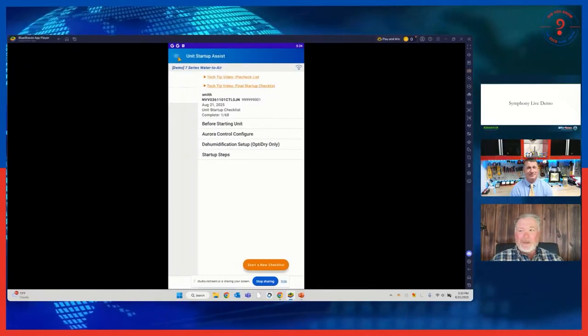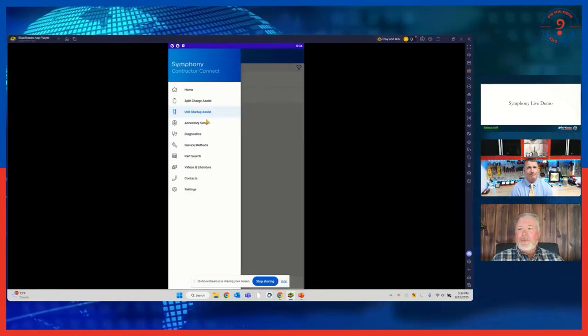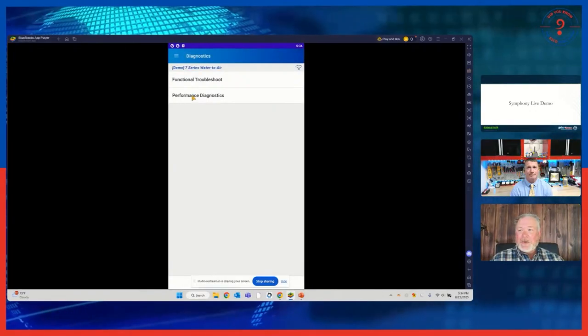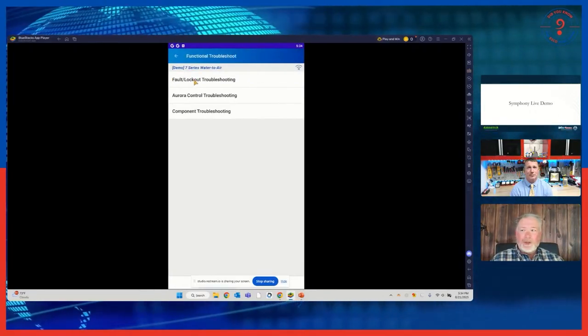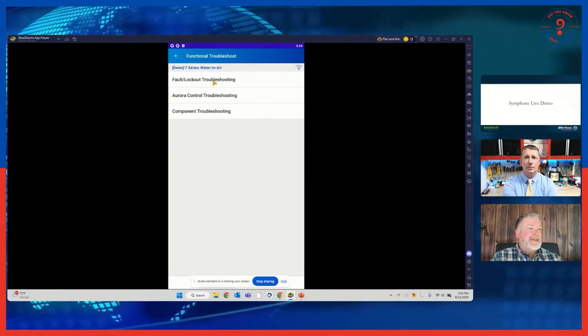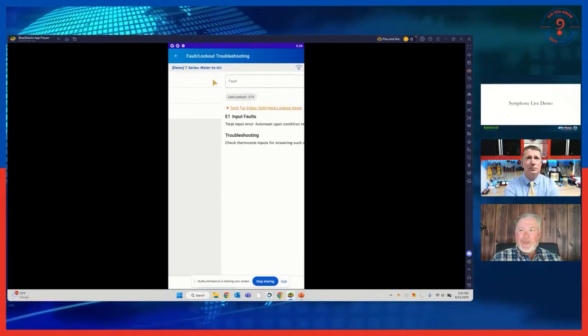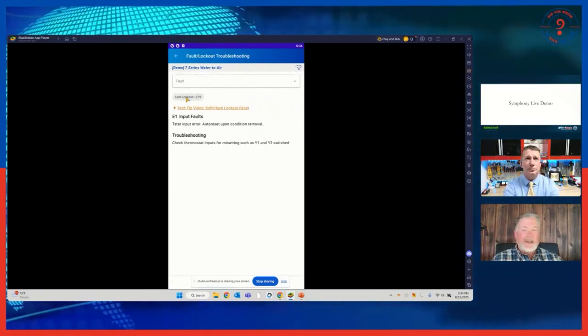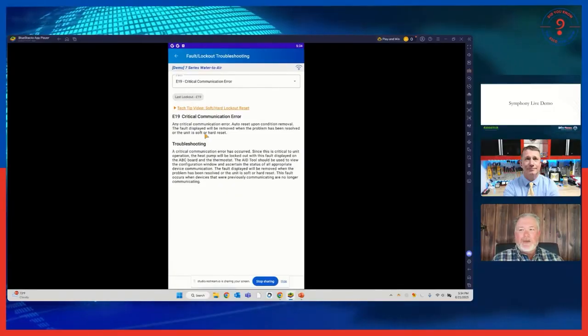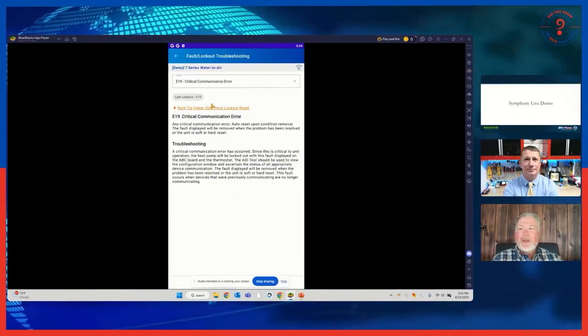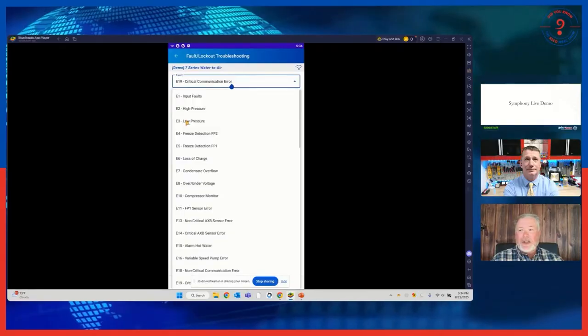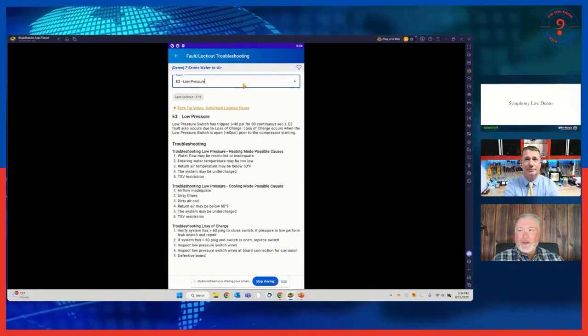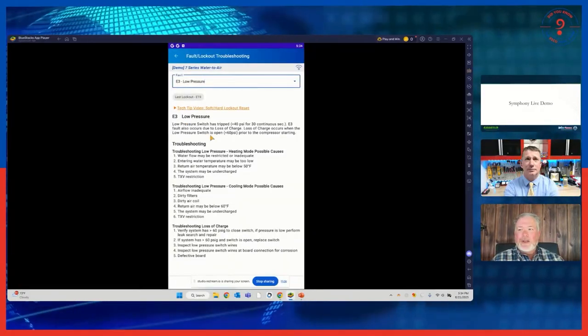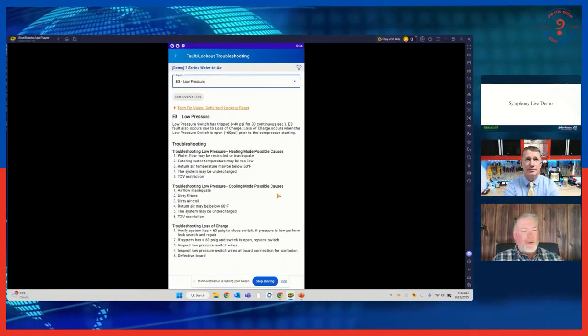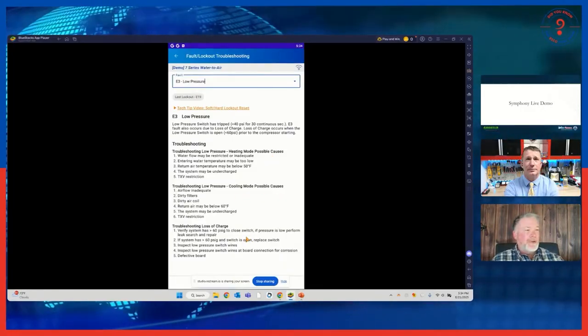So the startup checklist works really well. On the diagnostic side, we've got functional troubleshooting. For example, I mentioned an E19 fault earlier - the last lockout on this unit was an E19. If I click on that, it tells me what it is and how to troubleshoot it. If I see another error, like low pressure, which is an E3 fault, it tells me what it is and how to troubleshoot it in heating or cooling, or if it's a loss of charge situation.